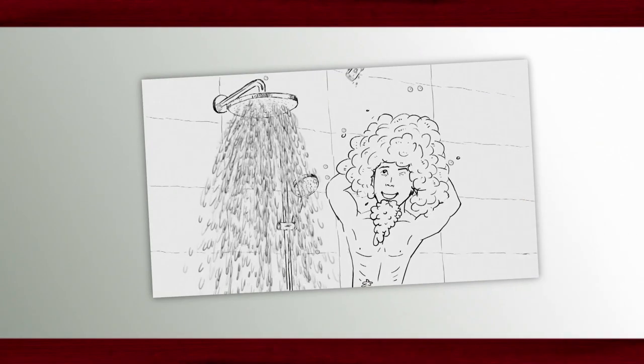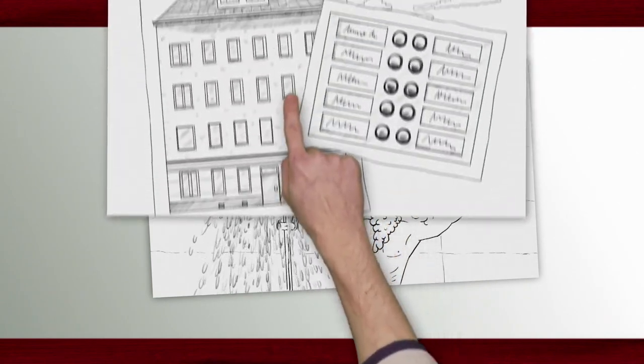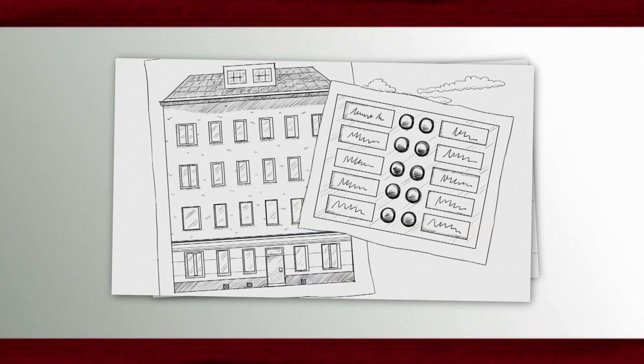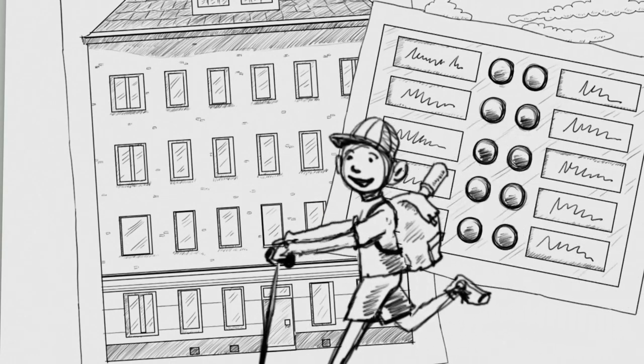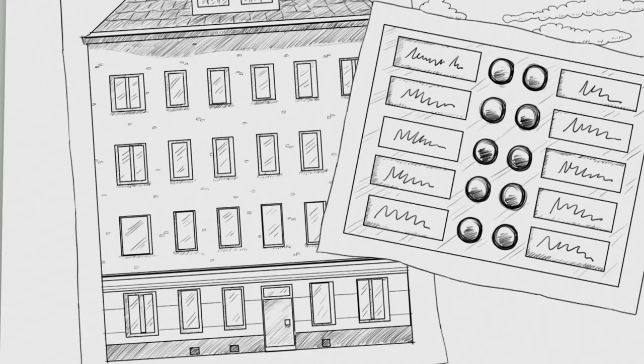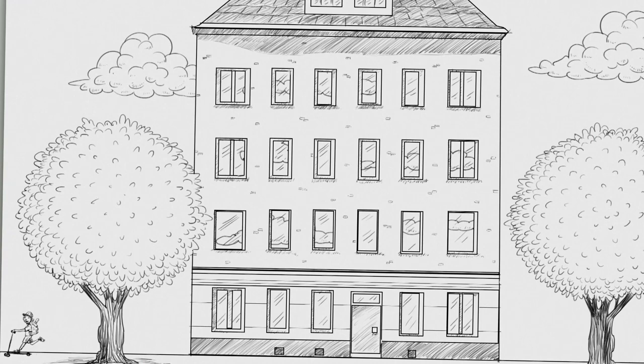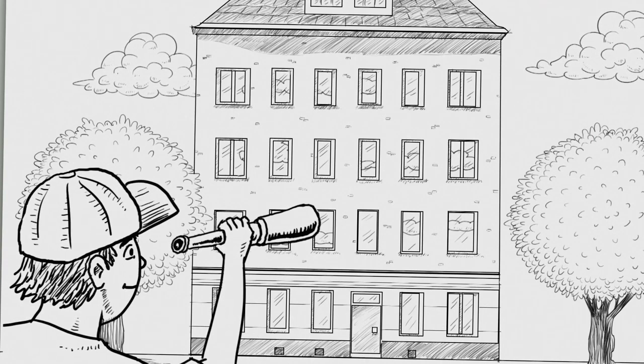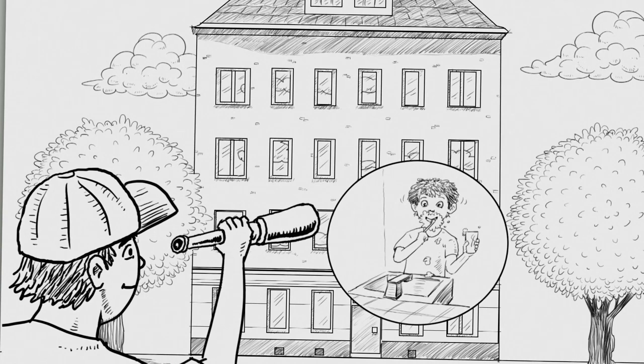For excellent hot water comfort, an instantaneous water heater needs a high connected load, but only for short periods. In the case of apartment buildings with 10 households using one instantaneous water heater each, this doesn't mean that the building needs a tenfold connected load. For instance, the German standard stipulates that generally only a few of the instantaneous water heaters are in operation simultaneously.